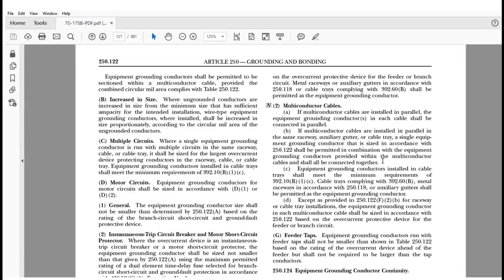Now you could, if you wanted, have a special brand. You can create what's called a paralleled MC product, and that just creates another SKU you've got to worry about. Or you have this provision. Now, let's understand that only this provision is going to allow that. If I still want to run two MC cables in a parallel application that doesn't meet these requirements, all right, that they're not run in the same raceway, auxiliary gutter, or cable tray, then I'm going to have full-size equipment grounding conductors, and that's going to be a special type of product that has to be made by the manufacturer for that properly sized equipment grounding conductor.